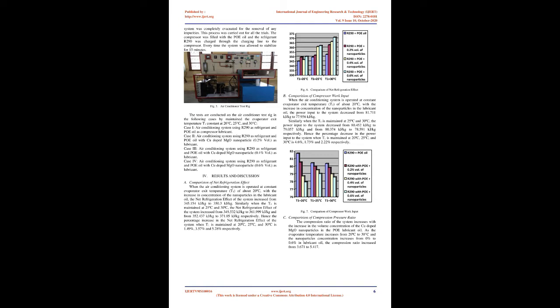The compressor was filled with the POE oil and the refrigerant R290 was charged through the charging line to the compressor. Every time, the system was allowed to stabilize for 15 minutes. The tests are conducted on the air conditioner test rig in the following cases by maintaining the evaporator exit temperature T1 constant at 20 degrees Celsius, 25 degrees Celsius, and 30 degrees Celsius.